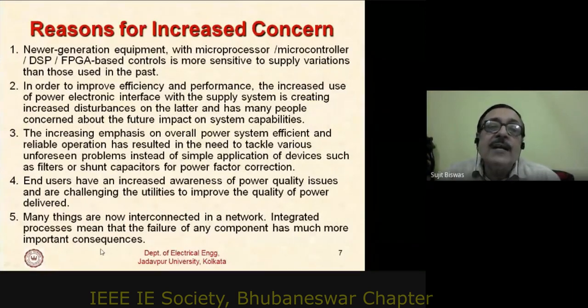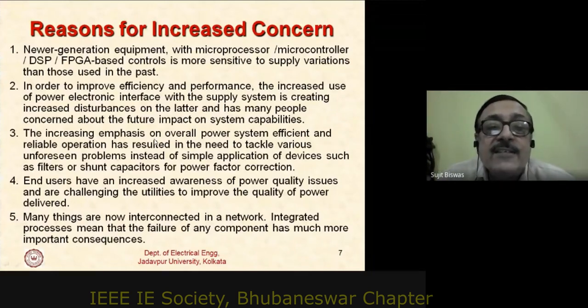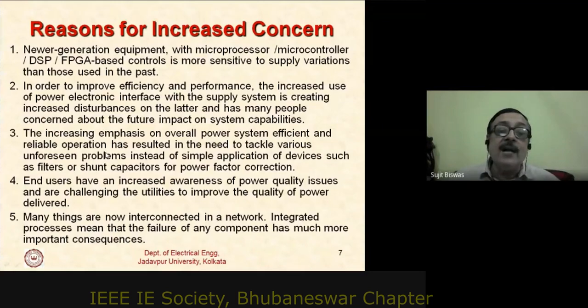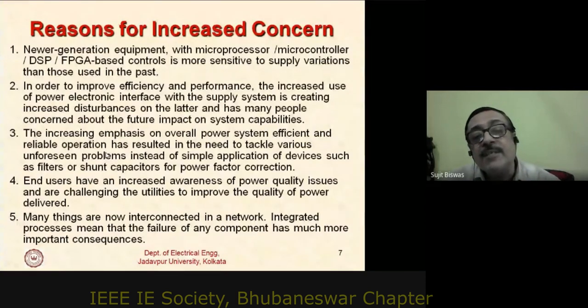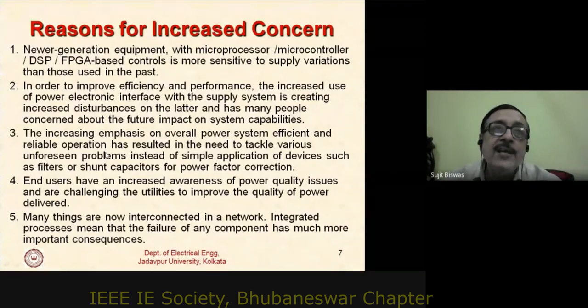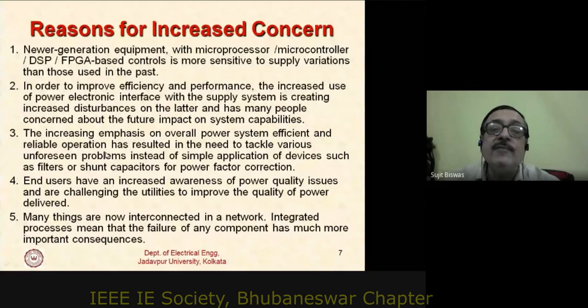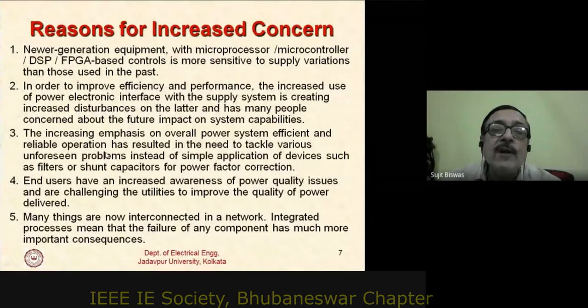The increased use of power electronic interfaces with the supply system is creating increased disturbances on the latter. For example, rather than running a motor at constant speed with a gear arrangement, we now use variable speed drives — achieving the goal but creating disturbances. Classically, power factor correction involved connecting capacitor banks, but today there are many problems with simply connecting capacitors to the line.